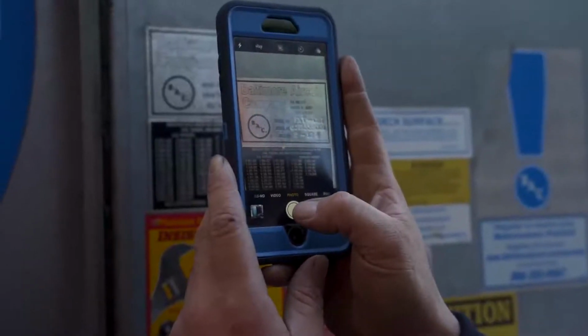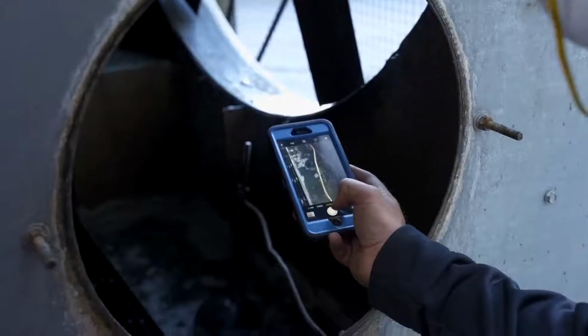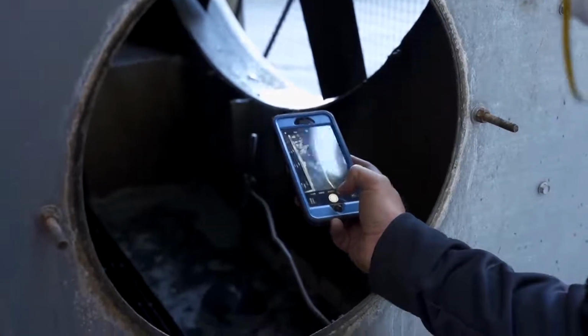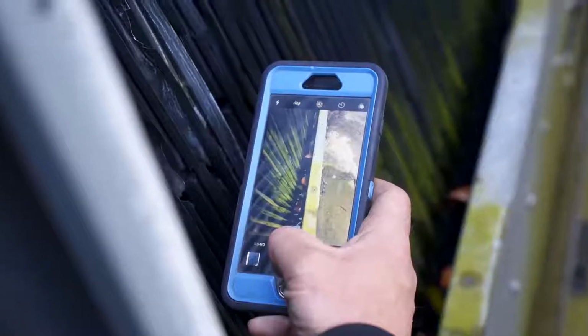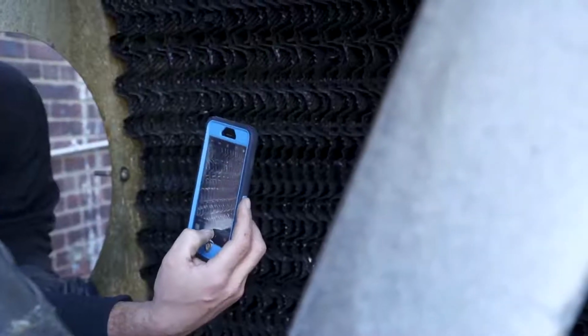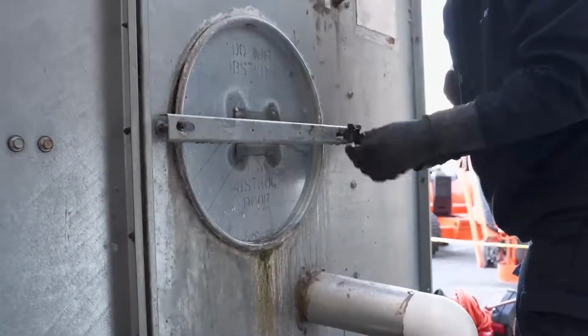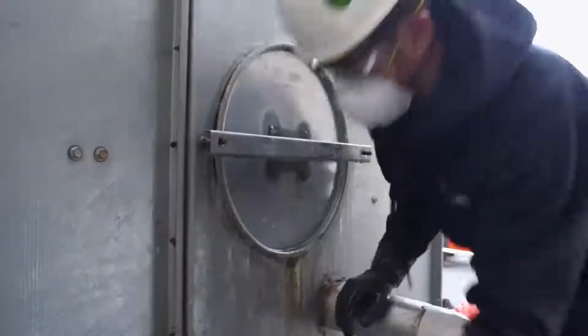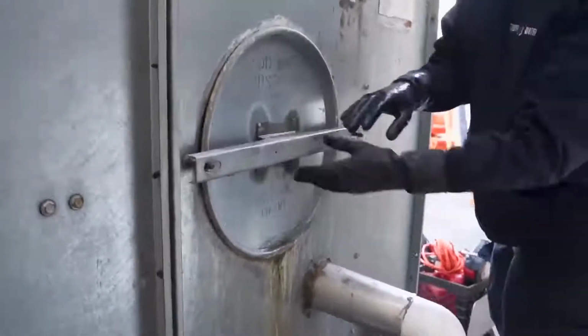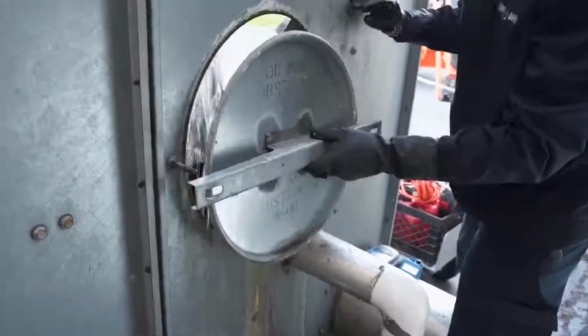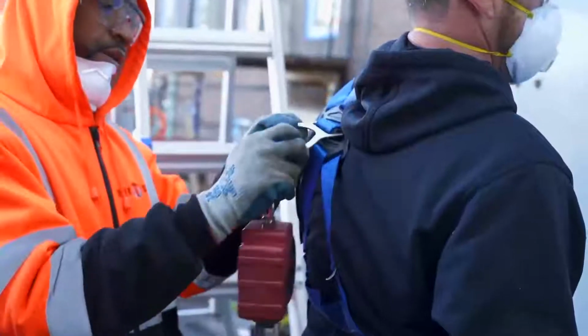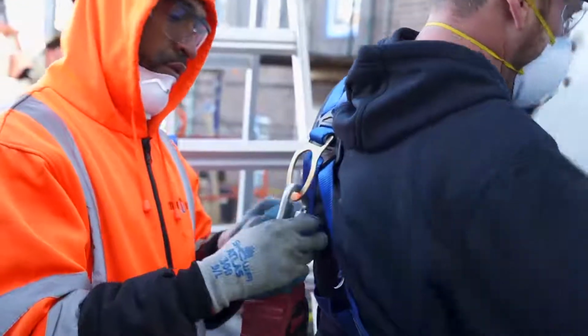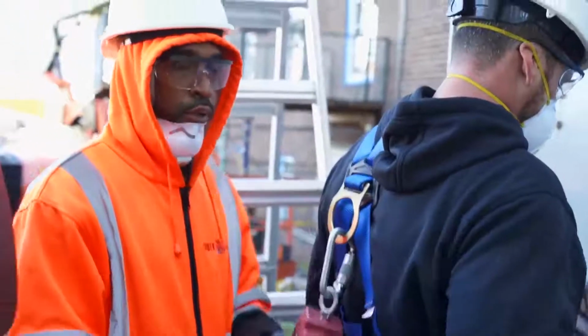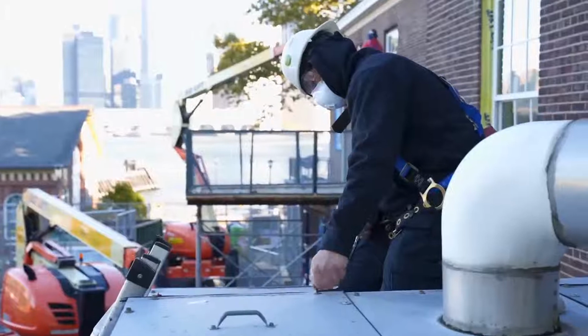Make sure to take photos of the system before cleaning, as we want to show the difference we made to the client. Before and after photos should be taken of the same location, at the same angle before and after cleaning. After an hour and your final test is completed, open the drain so that the basin and sidewalls are exposed. Before going to the top of the cooling tower to inspect it, put the rest of your PPE on, including your safety harness and fall protection.